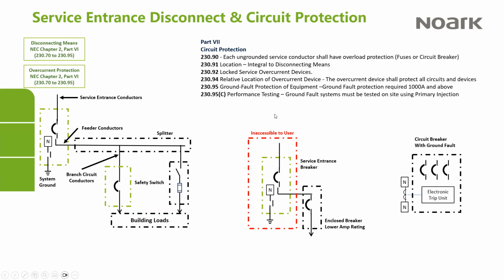Right. So then the last bit here, yes. The last bit here is ground fault protection. Any circuit breaker that's at 1,000 amps or greater requires ground fault protection. And the follow-on piece of that is clause C under 230.95. Those ground fault systems must be tested on site using primary injection means. So I'll just give you a quick overview of that.